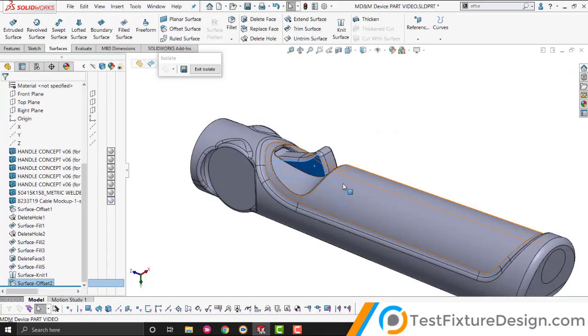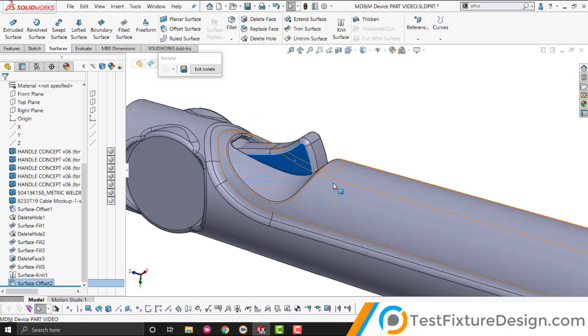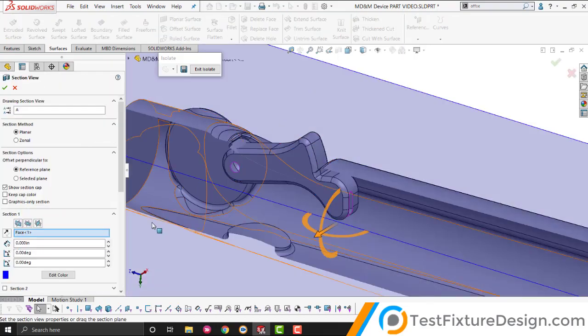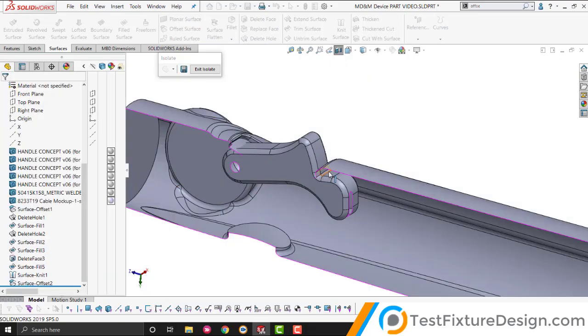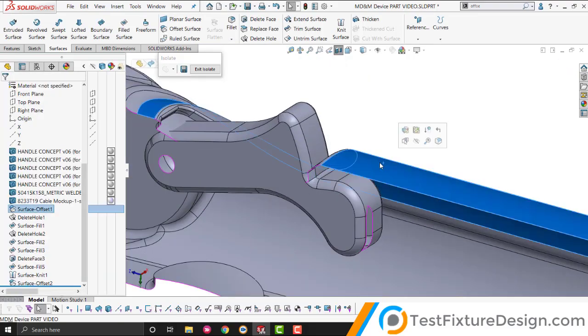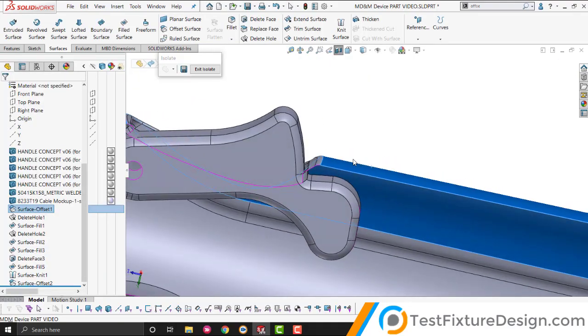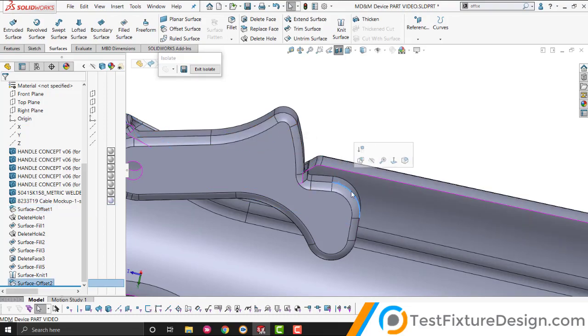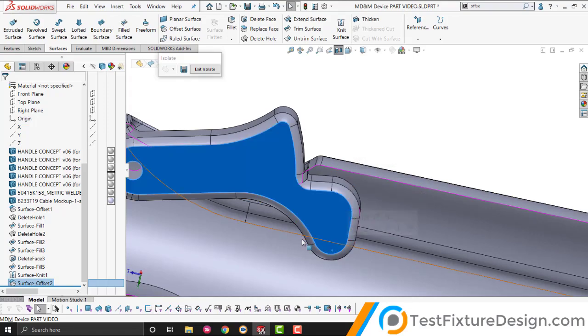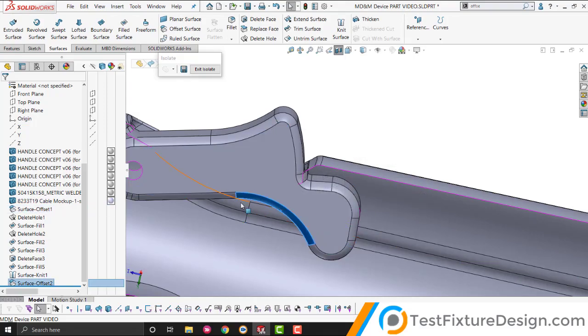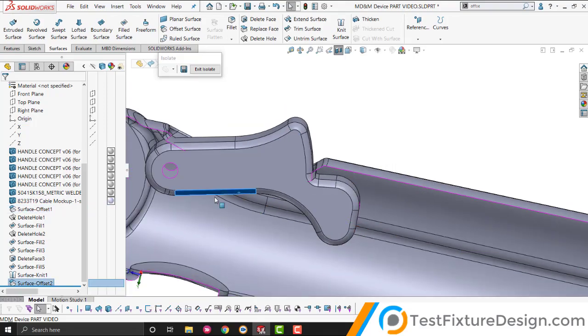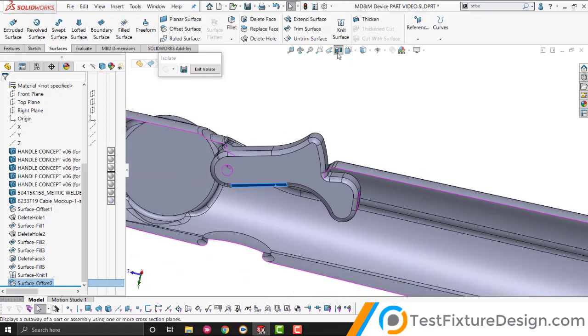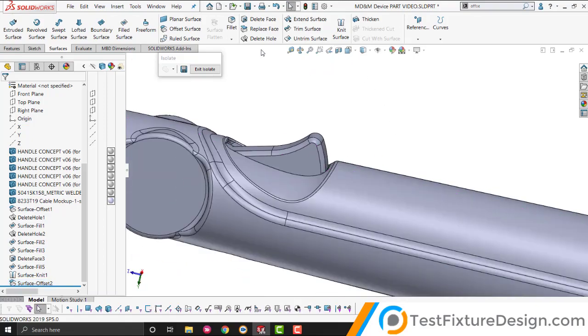Now, we want to get rid of the lower portion of the trigger. This part that's on the inside. Let's do a cross section. Let me show you what I mean. So, this external surface is out here. We want it to come right back around and all of this to be external surface. Therefore, we want to get rid of all these surfaces inside the medical device. Because we don't need them. And to do that, we're going to use the trim surfaces.